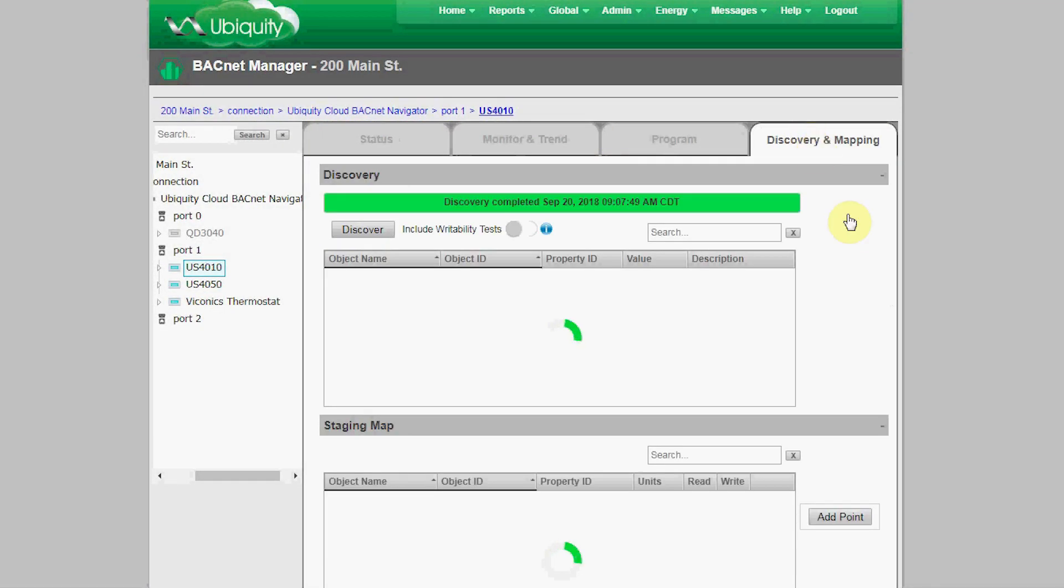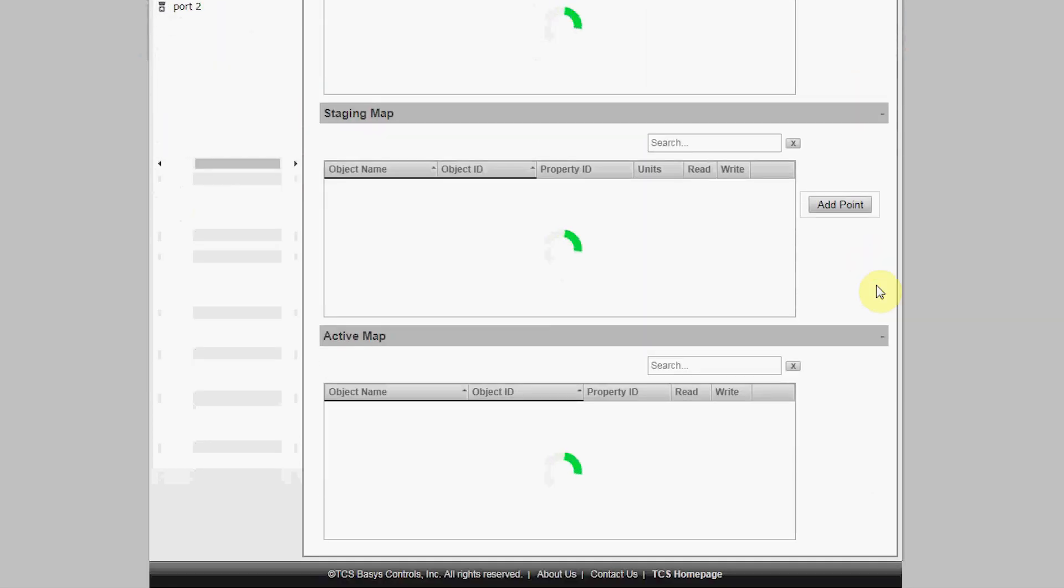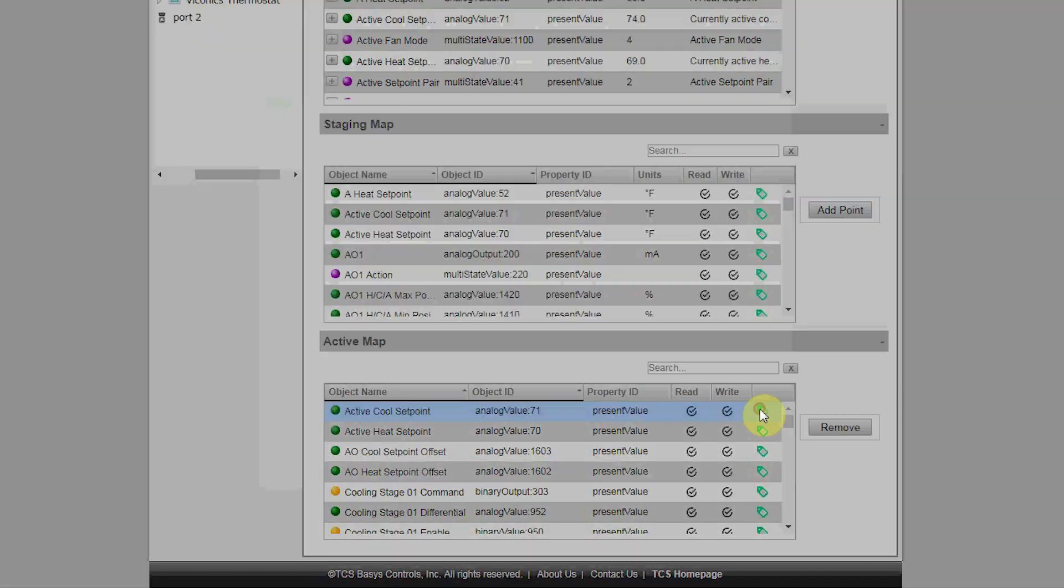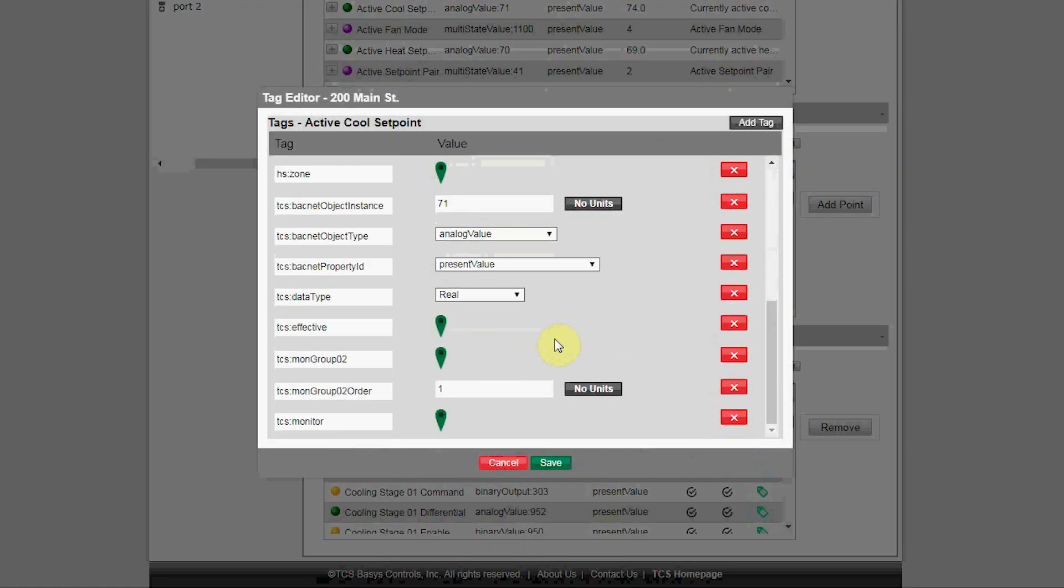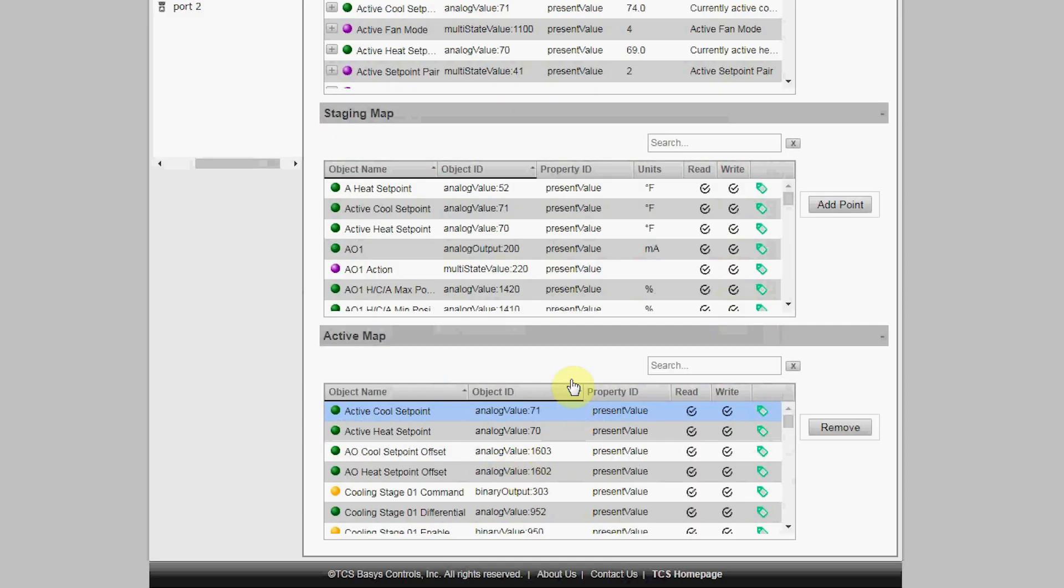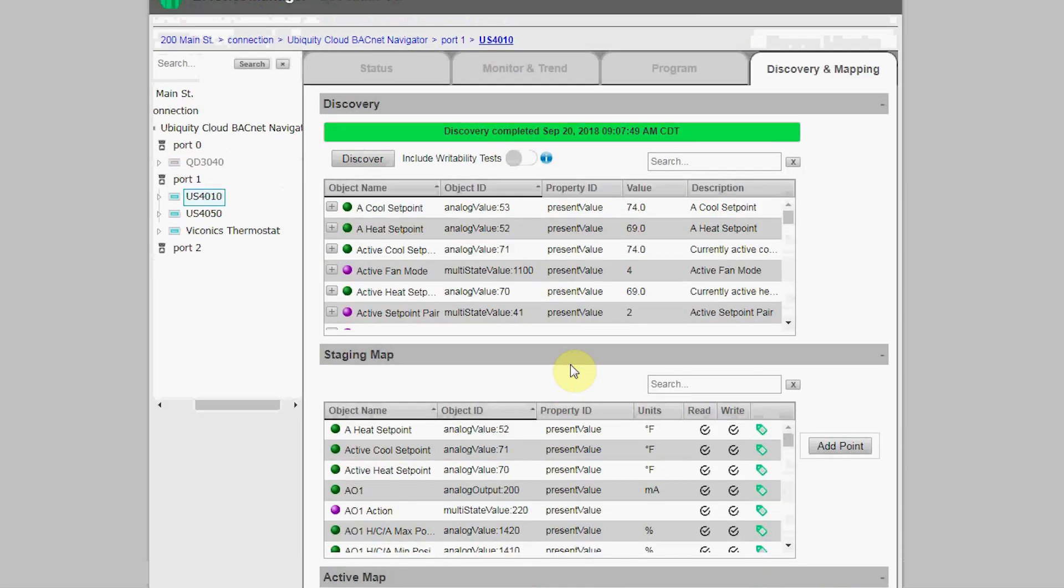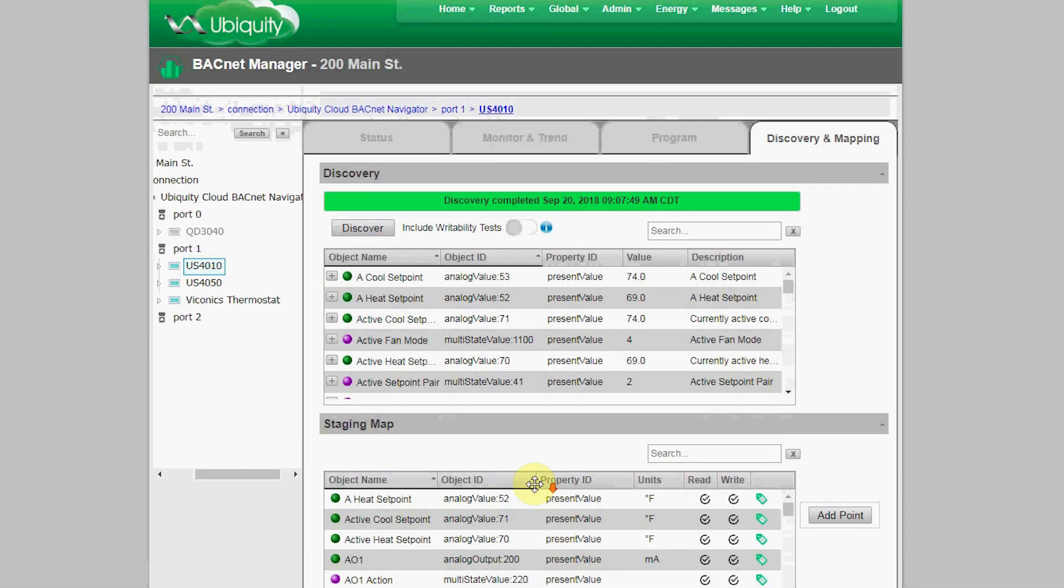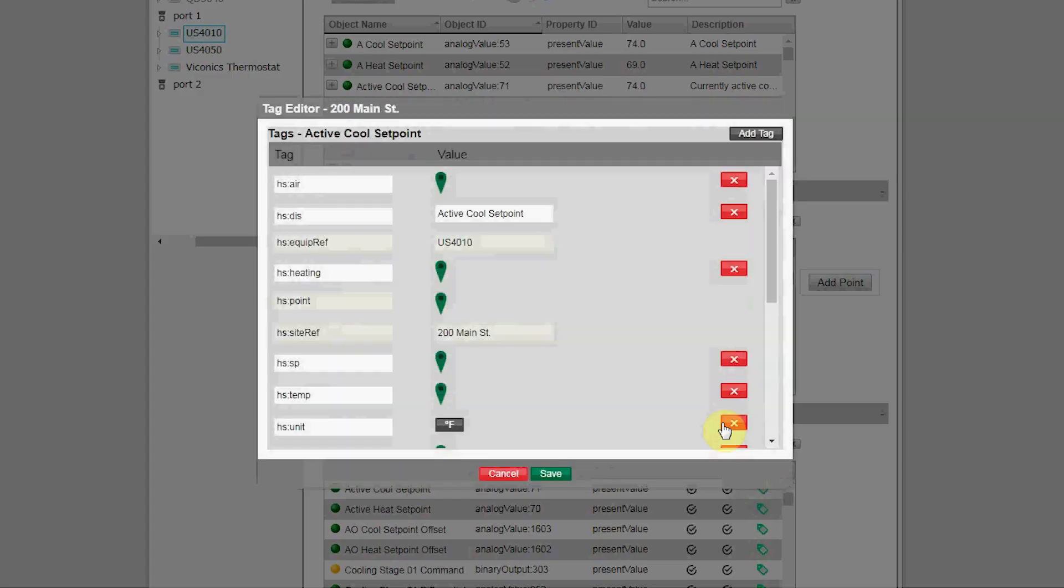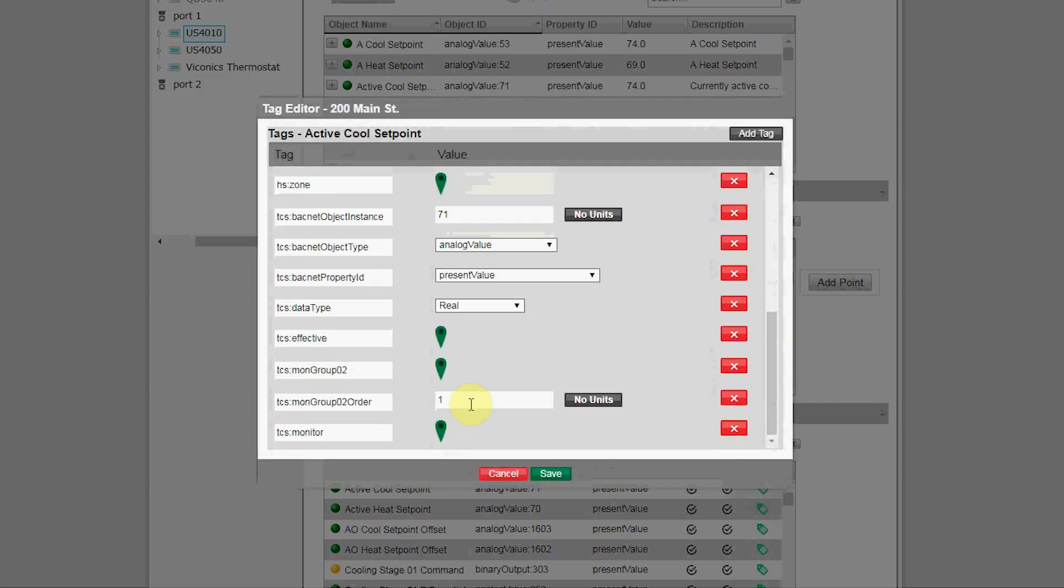Then I went to the points and used the tag editor to delete any points I didn't want to appear on the monitoring or programming pages just by removing those tags. Then finally, for the points I actually wanted to appear on the monitoring and programming screens, I updated those tags. As you can see, for the active cooling setpoint, I assigned the monitoring tag, then assigned this point to be in the second monitoring group—in this case, Active Set Points—in the first position.